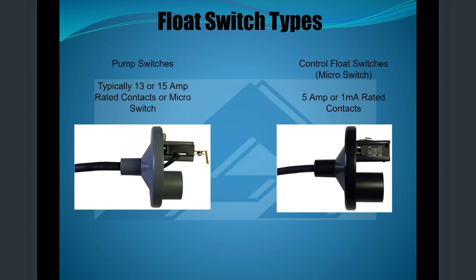On the left, and these are our old pump switch and control switch models, our big switch and our Unimax. So on the left is our big switch that has metal contacts, which can take on those full load amps of the pump. And technically it would work for a limited time with a control circuit, but over time there would become a residue that would build up over those metal contacts that would eventually stop allowing that to work. But it would work in a pinch for a short duration on a control circuit if you wanted to connect it to alarm, but I wouldn't recommend it.